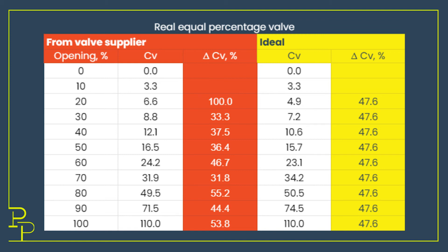You can see that if it followed the equation perfectly it would have a constant increase in CV of 48% for every additional 10% that the valve opens, but the actual change varies between 33 and 100%.